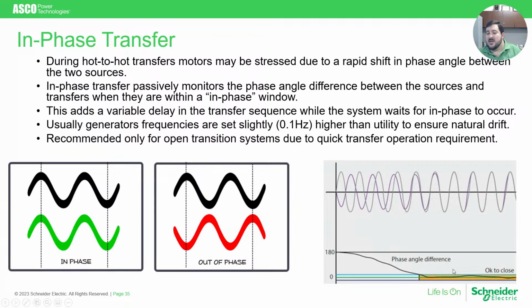That's important because by making sure the two sources are closely synchronized, it minimizes the number of electrical transients to your system, especially when you have large inductive loads such as motors and pumps. So it helps prevent nuisance tripping of breakers on those pieces of equipment and protects them from physical damage due to those transients if you do transfer out of phase from one source to the other.